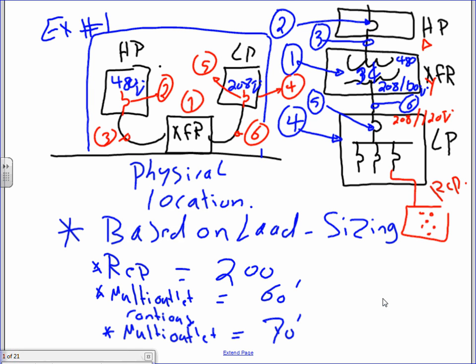We have a main panel that we typically call a high voltage panel because it's 480, feeding a transformer that feeds a low voltage panel, which is 208/120. In the project that we have, Karen, we have 2 of this type. If you guys remember, we have one for the receptacle panels that you guys are going to be circuiting soon, next week. Same combo.